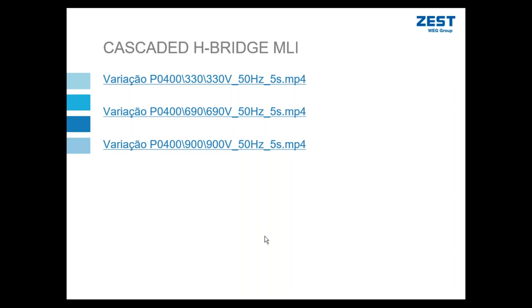One particular advantage to an H-cell multi-level inverter can be demonstrated by a solution that we supplied to SABS for their pump test bay. What we supplied to them was a multi-level H-cell inverter that is capable of switching at its maximum 11 kV. But it is also able to switch at reduced voltage outputs, even at maximum frequency. So they are able to use this drive to test multiple pump motor systems from 3.3 kV, 6.6 kV, and higher up to 11 kV using the exact same VSD and still obtaining maximum frequency and output voltage for that specific motor. I've got some videos just to demonstrate the actual measurements of the waveforms.